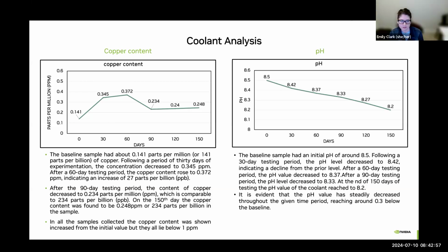Before you go to the next slide, just a couple of questions. You said that the copper content stayed below 1 part per million. Is that the level of goodness? Is that the requirement that it stay below that, or is that just...?